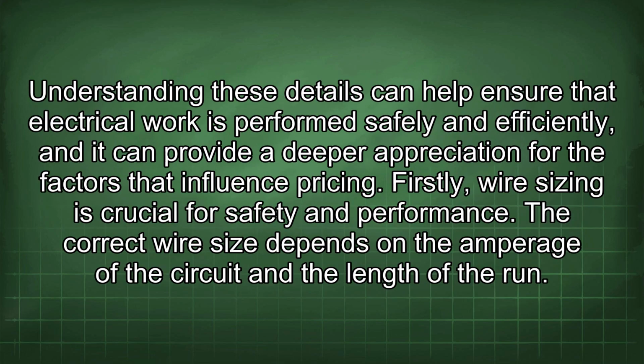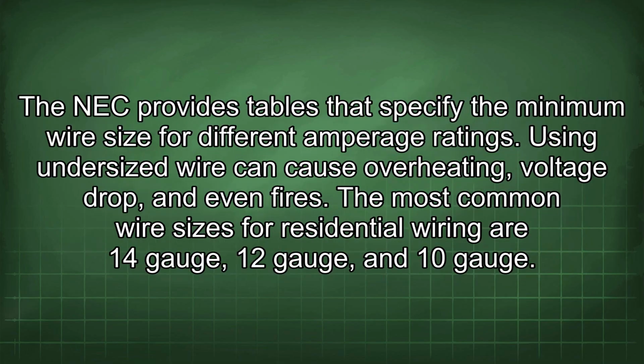Understanding these details can help ensure that electrical work is performed safely and efficiently, and it can provide a deeper appreciation for the factors that influence pricing. Firstly, wire sizing is crucial for safety and performance. The correct wire size depends on the amperage of the circuit and the length of the run. The NEC provides tables that specify the minimum wire size for different amperage ratings. Using undersized wire can cause overheating, voltage drop, and even fires.